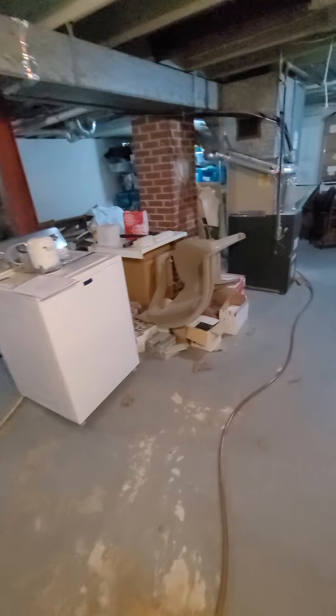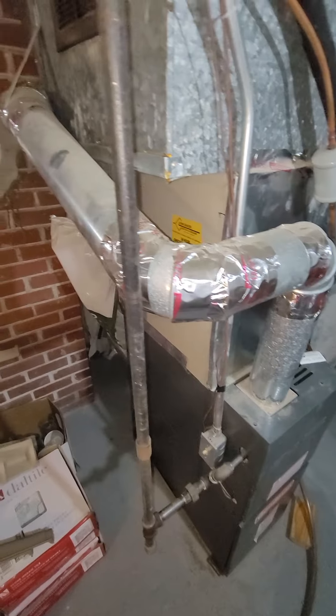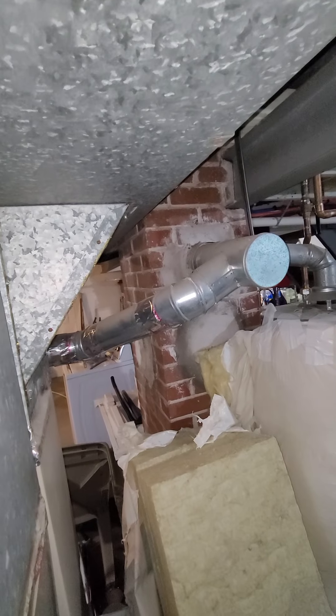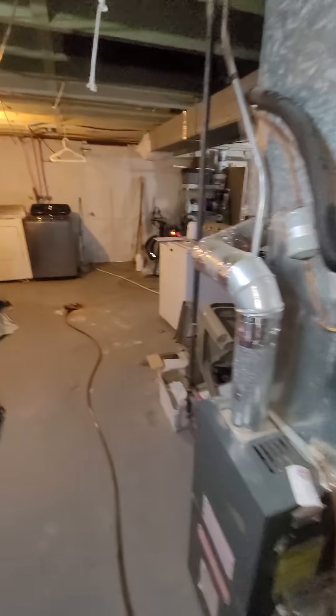The unit itself over here — you've got a four inch flue with a three inch flue on the water heater. So you've got a three, four, five on the clean out, and the flue liner looks newer, so we don't need a flue liner.